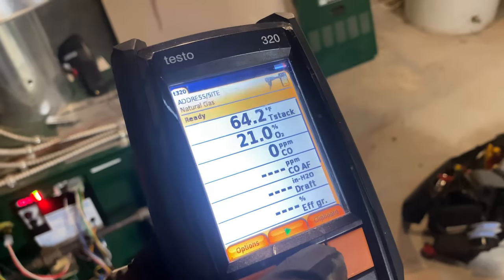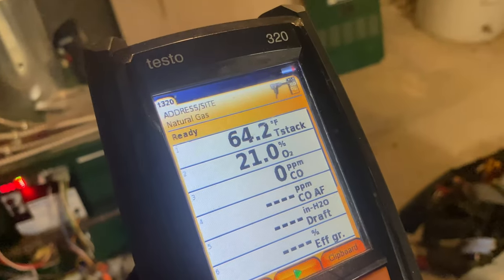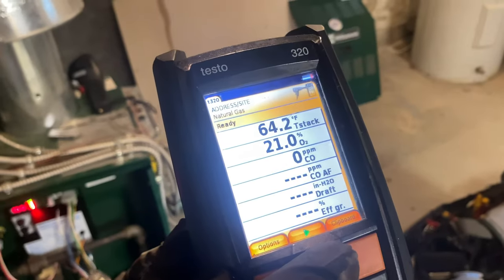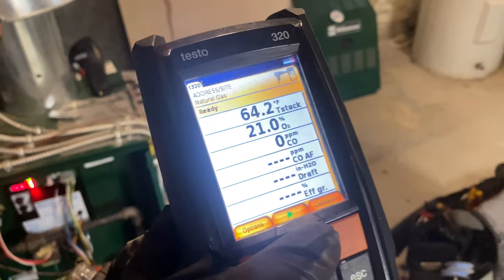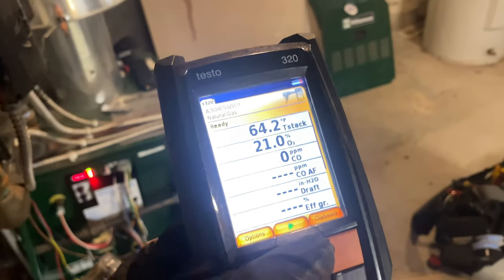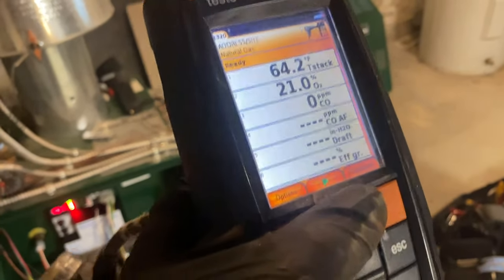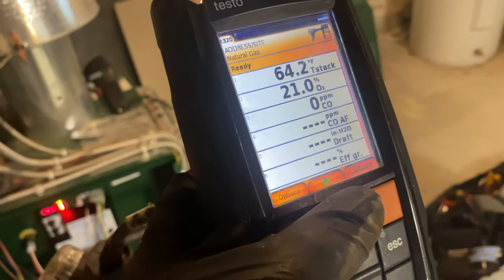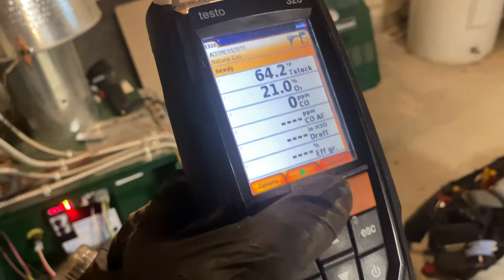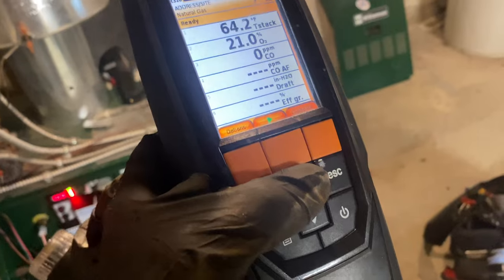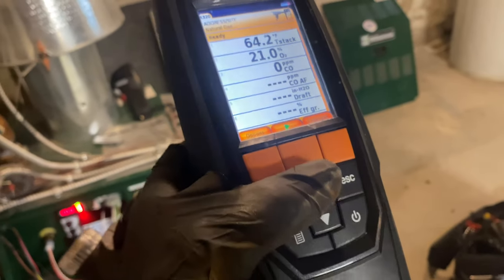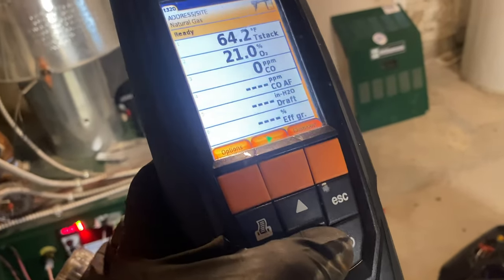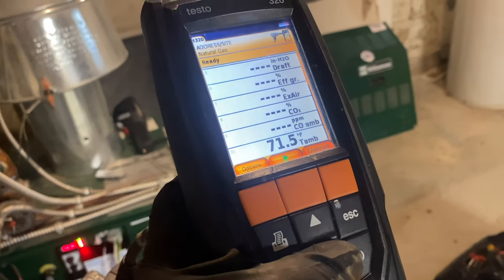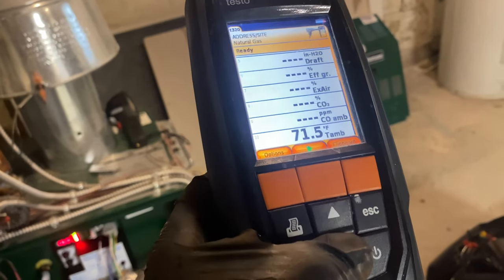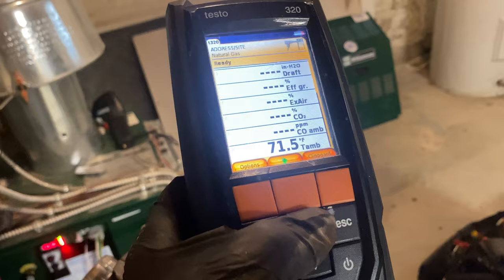Right now we're reading an ambient temperature or temperature of stack, which is the probe, of 64.2 degrees. We're at 21% oxygen, which is what you're breathing in right now—21% is O2, actually 21 and a little bit of change, but 21 is O2. We're also reading zero parts per million of carbon monoxide. I have some other numbers that are dashed out, but actually ambient is right there at the bottom, 71.5, sorry.